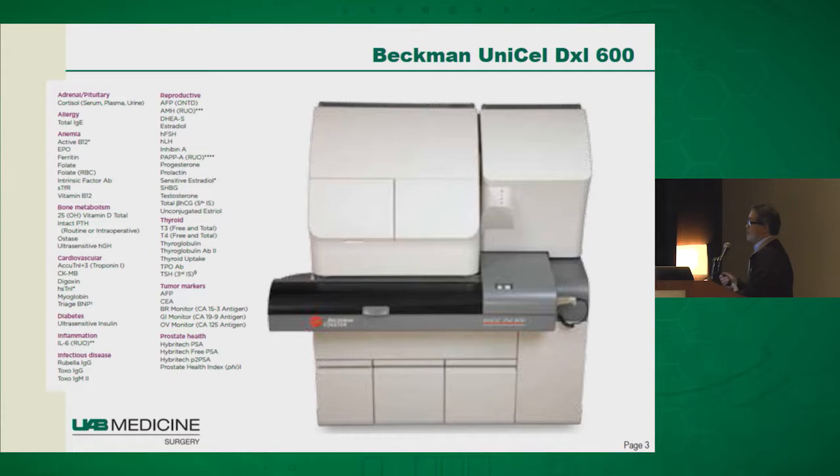There are many types of PTH testing machines commercially available. This is the one we use at UAB — it's called the Beckman UniCel DxI 600, which sits in our core lab. It's very economical for the hospital because in addition to PTH testing it performs many different endocrine tests, generating revenue. Most hospitals have this sitting in their core lab, and you either tube down samples or have a runner, making it very economically positive.